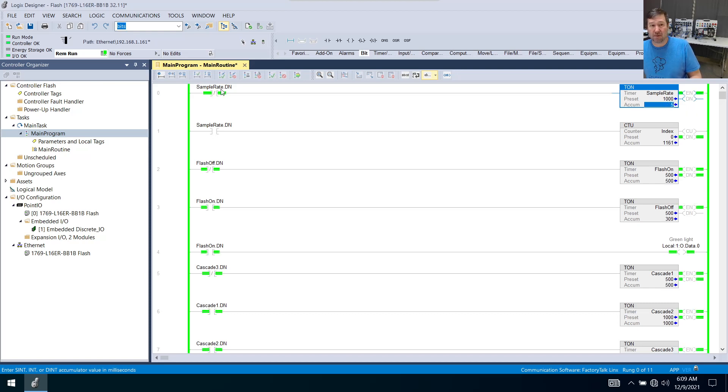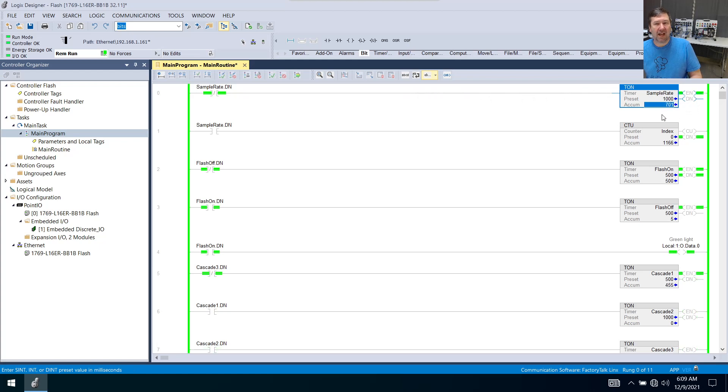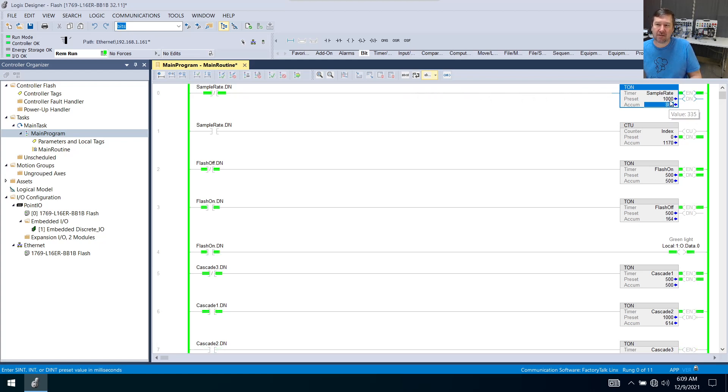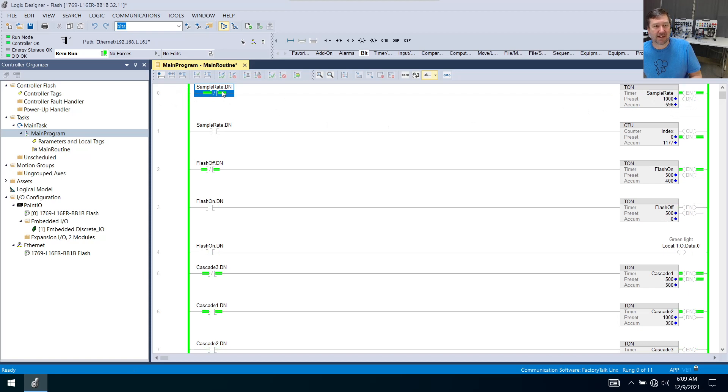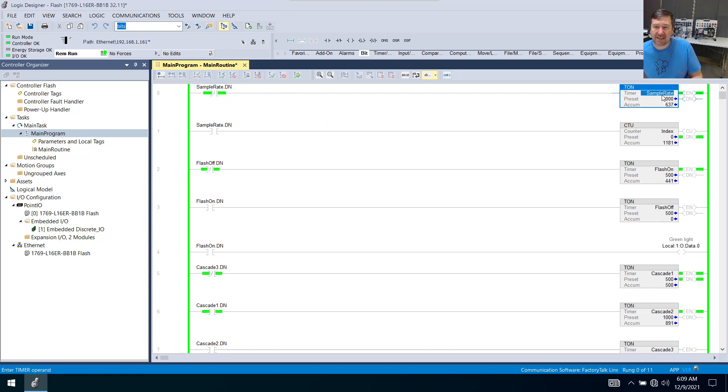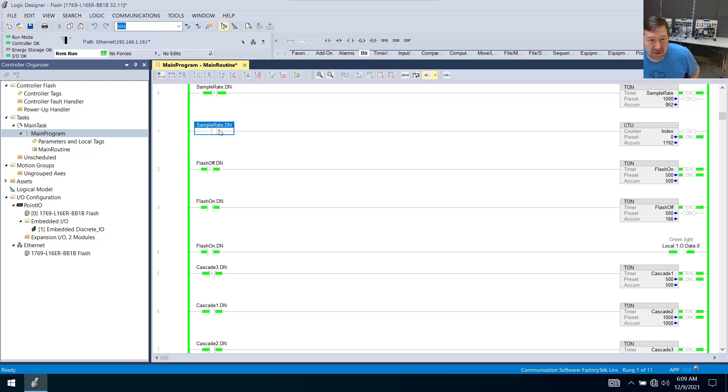So we're looking for a zero here. So if it's not done, our timer is going to be true. And then the moment that the accumulated value is greater than or equal to 1000, it is going to set the done bit. So understand that when this rung started scanning, the done bit was false. And in that instance, then it set the done bit to a one. So that means for this single scan, this go look for a one is going to be true.